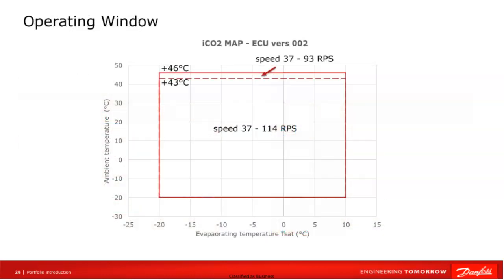On this slide, we present the operating envelope of the iCO2 condensing unit 4.6 kilowatt. We note that the evaporation temperature range is from -20 to 10 degrees Celsius. The maximum ambient temperature at which the unit can operate is +46 degrees Celsius, with the rotation speed limited to a maximum of 93 revolutions per second. This is important information that helps you understand under what conditions this unit can operate effectively and allows you to properly adapt it to a specific application. Now we will move on to further details related to the functionality of this unit.